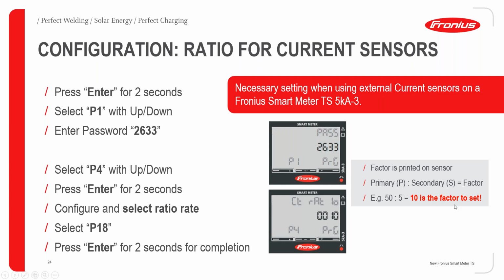So normally factors will be printed on the sensor directly, or it will say the primary and secondary side values. Then you have to enter this factor into the smart meter display. Then it's the same way. If you press enter for 2 seconds, then you can go to the program menu of the smart meter. Otherwise, if you use up and down, you will simply see the values of the smart readings in the smart meter. So whenever you want to configure something, you have to press enter for 2 seconds so that you will be inside the programming menu.